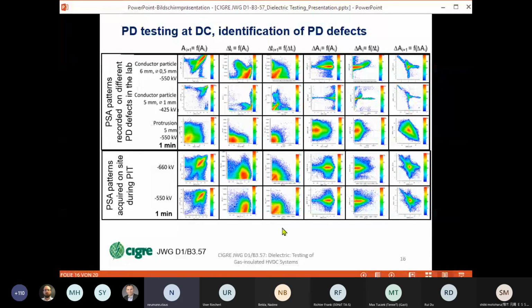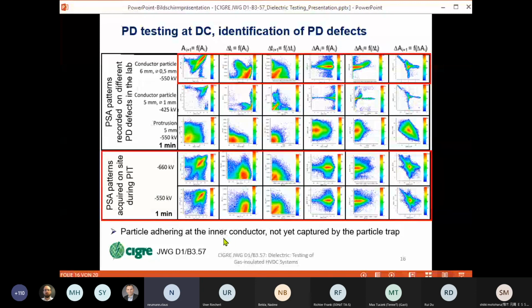I want to compare that with patterns acquired during the prototype installation test. You can see there is a certain equivalence between the first row gained in the lab and these rows recorded at the prototype installation test on site. The conclusion is that particles adhering at the inner conductor are probably not yet captured by the trap.